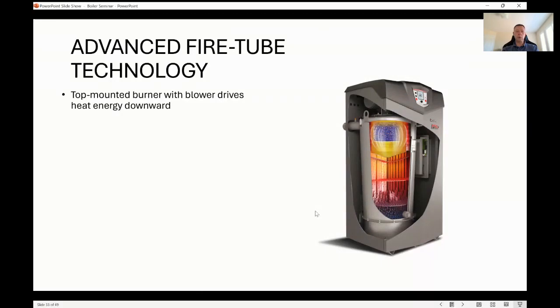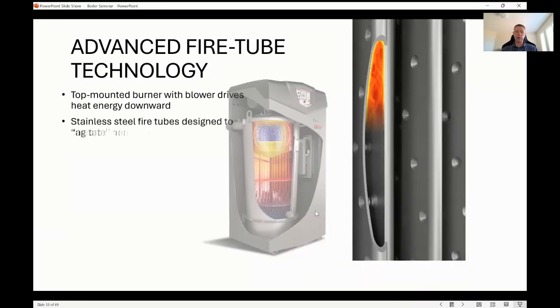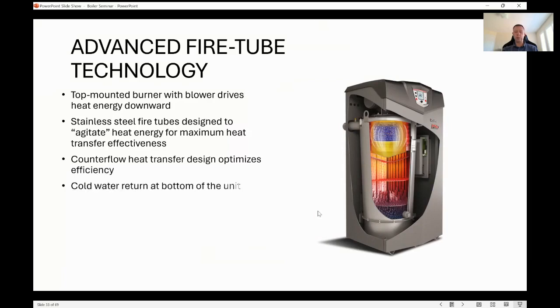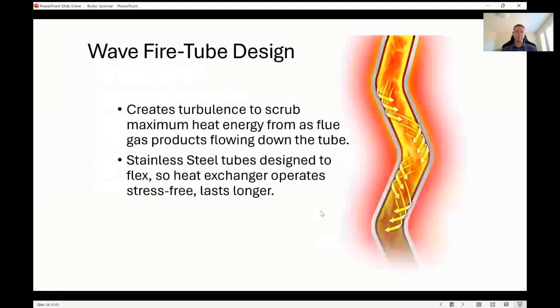So taking a look here, most of these fire tube designs are a kind of counterflow design as well. You'll find that as most condensing boilers will have it. They'll have the burners at the top, which is going to be the hottest portion of the heat exchanger. The flue products go through the tubes. The tubes here have these dimples in them. That's not the only way to accomplish this, though. You're going to maximize your heat transfer coming out of there. Generally a counterflow design, so that cold water comes in the bottom first. Most of your condensing is going to be occurring at the bottom portion of this heat exchanger. It's almost raining in that portion. It'll be collected and piped to the outside. As you get towards the top, you're not going to condense the closer you get to that burner. You're still putting a lot of heat into your thermal balance though.